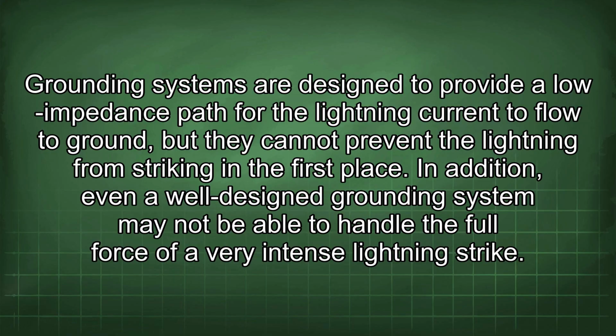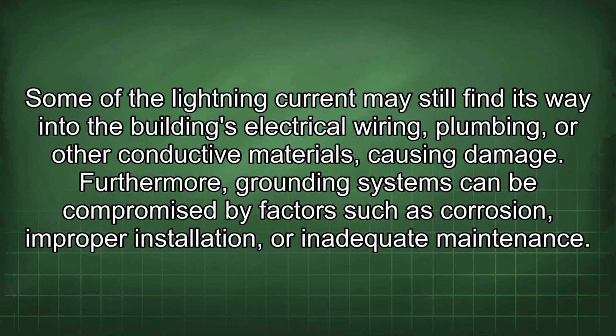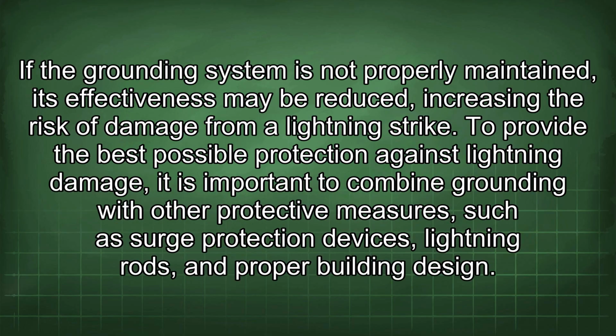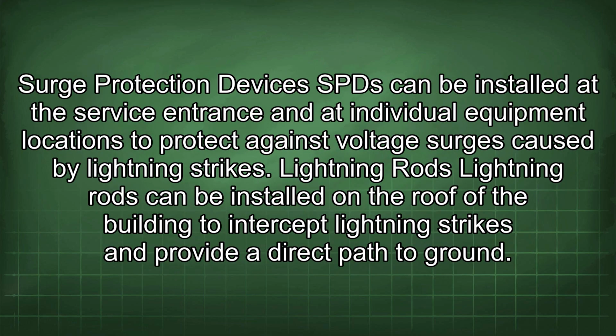In addition, even a well-designed grounding system may not be able to handle the full force of a very intense lightning strike. Some of the lightning current may still find its way into the building's electrical wiring, plumbing, or other conductive materials, causing damage. Furthermore, grounding systems can be compromised by factors such as corrosion, improper installation, or inadequate maintenance. If the grounding system is not properly maintained, its effectiveness may be reduced, increasing the risk of damage from a lightning strike. To provide the best possible protection against lightning damage, it is important to combine grounding with other protective measures such as surge protection devices, lightning rods, and proper building design. Surge protection devices (SPD) can be installed at the service entrance and at individual equipment locations to protect against voltage surges caused by lightning strikes.